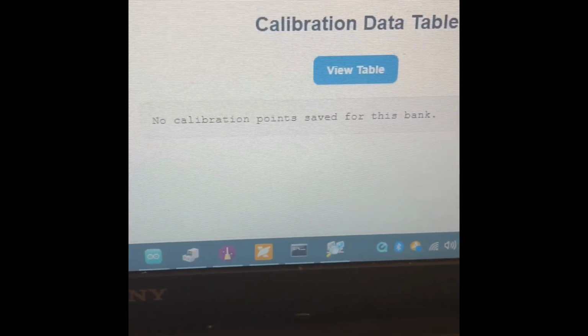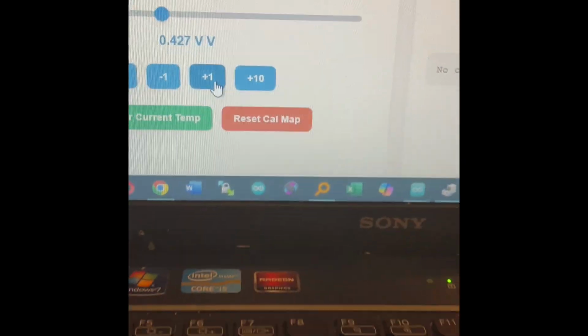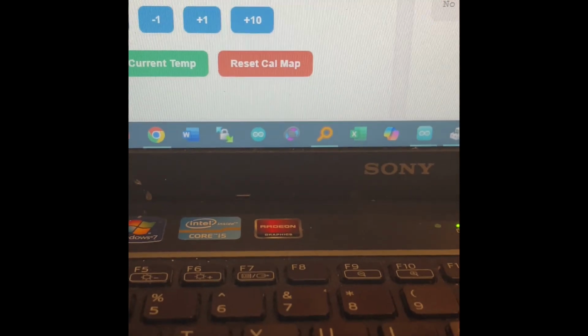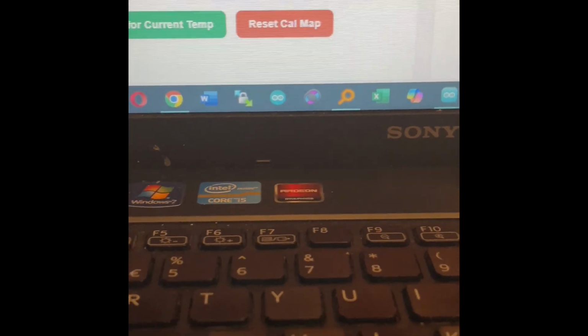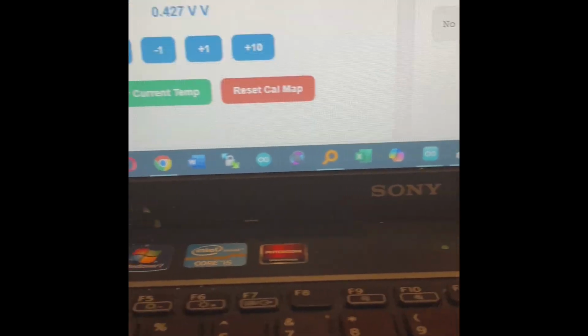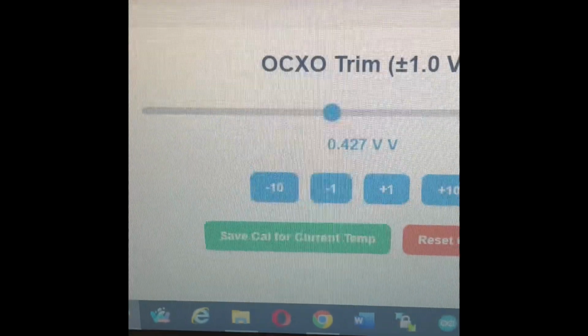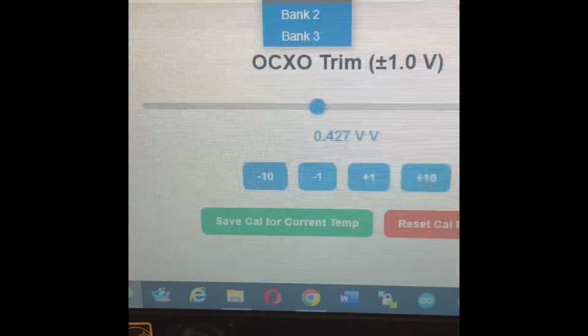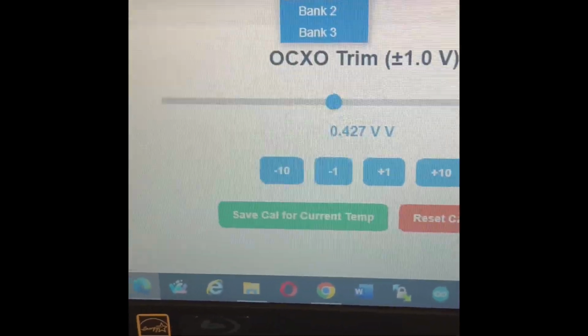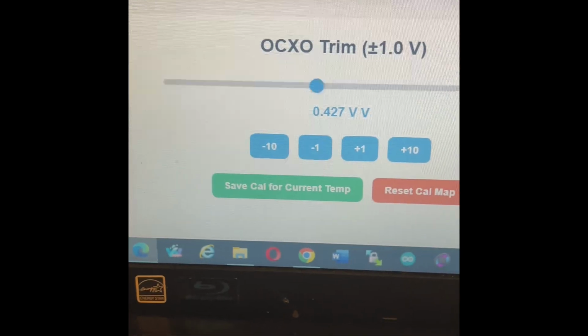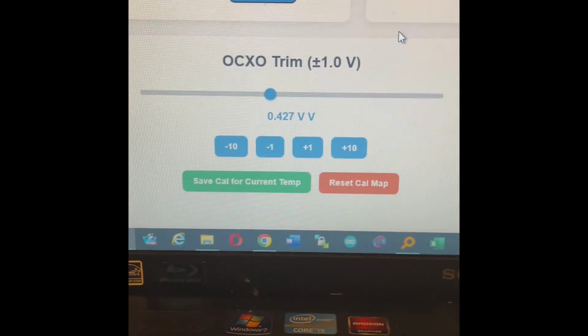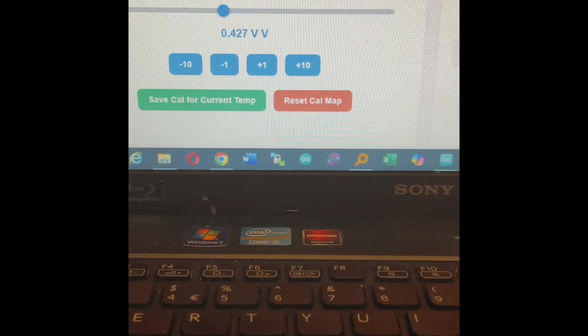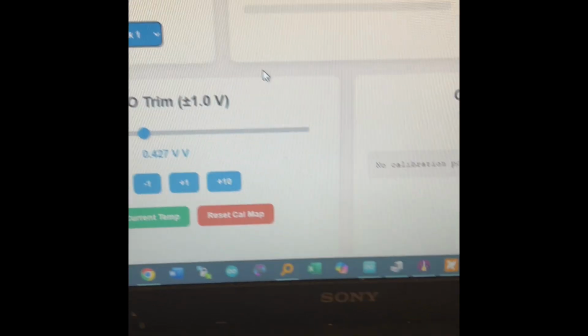No calibration points saved for this bank. And if I go up, there's actually 3 banks that we can refer to. So hold a second. So down, and then we have a calibration plot as well. So there we are. I think I might have, oh there we are, sorry, I've moved it around a little bit. And then if we click on bank 1, we have 3 different banks of calibration data. Say if we want to use some sort of external reference, there might be calibration between a certain temperature from switch on, from warmed up after 10 minutes and warmed up for 20 minutes. We can just simply change our banks around.